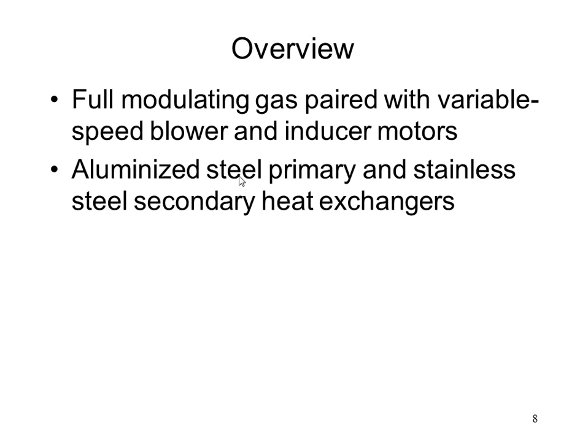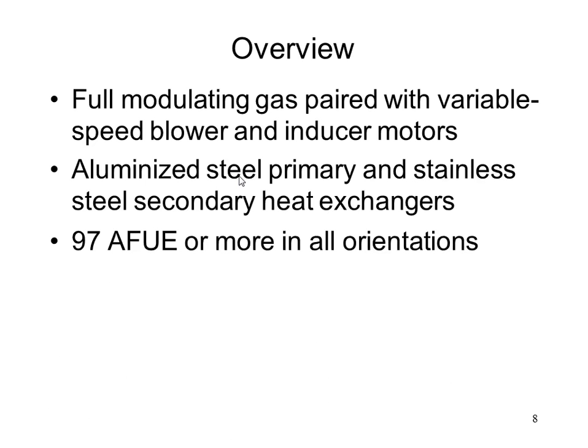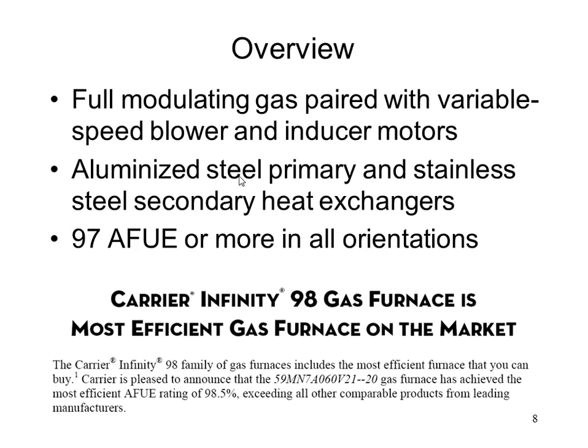The heat exchanger is an aluminized steel primary heat exchanger like we have done traditionally on Carrier and Bryant furnaces. However, unlike the traditional furnaces, the secondary heat exchanger is a different type of design. It is a stainless steel fin and tube type design, and I'll show you some pictures of that in a little bit. Efficiency is fantastic.